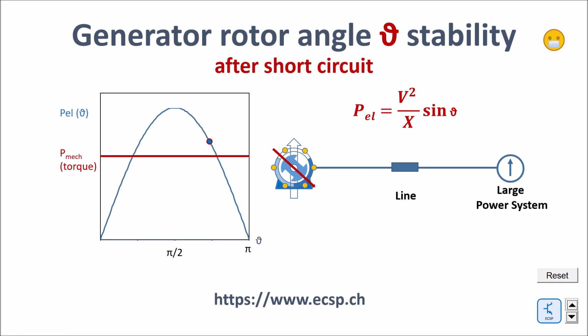If not, we will lose control of the speed of the generator. In this case unfortunately we do lose control and the generator just accelerates. That means we would have to close the valves of the generator to slow down the motor, stop or brake the generator's rotation, take away the torque, and re-synchronize the generator with the grid before we can re-close it and start delivering power again.